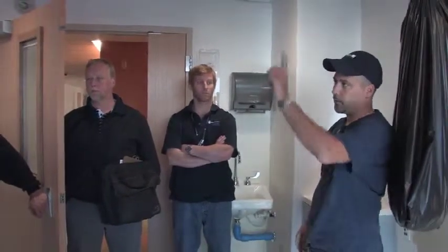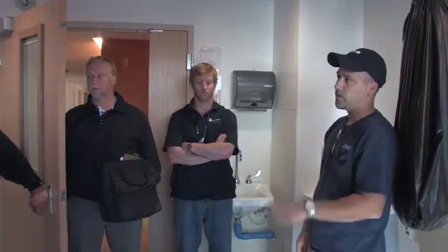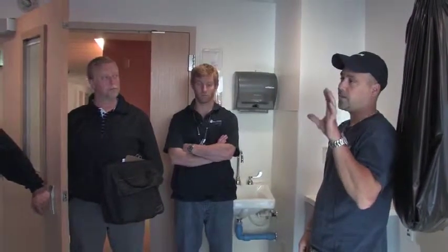There was a power issue on the floor with the type of circuit that was run, which had to be in pipe. The solution that the hospital engineering and everybody came up with is that they put in transformers. So we have 3 to 4 transformers per floor. The VAV boxes have 24 volts going to them. It's 110 at these transformers that you'll have in the hallway, and from the transformer they use the existing wiring for the 24 volts that's powering all of these. So you're not going to have 110 volts per VAV.